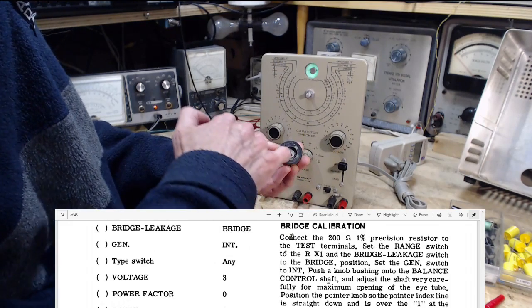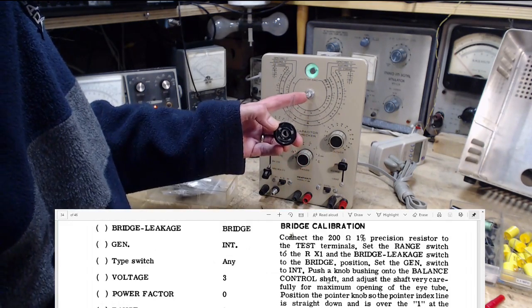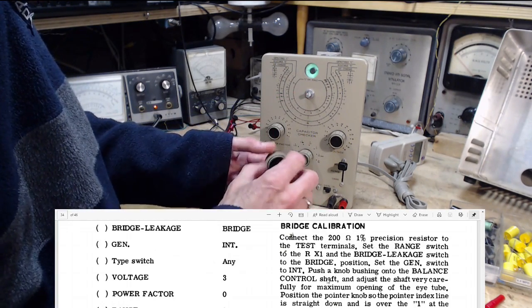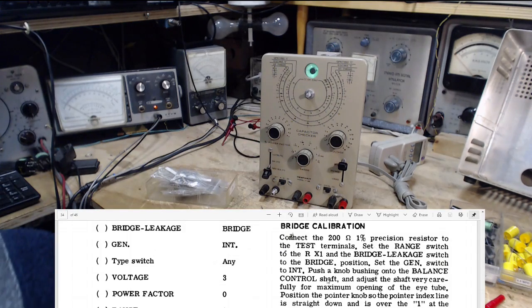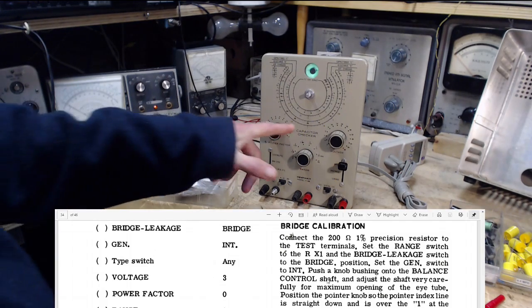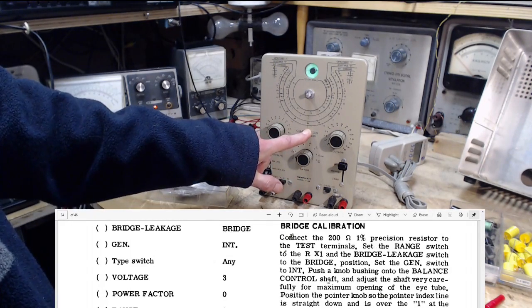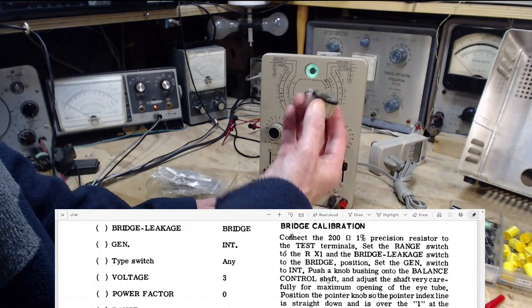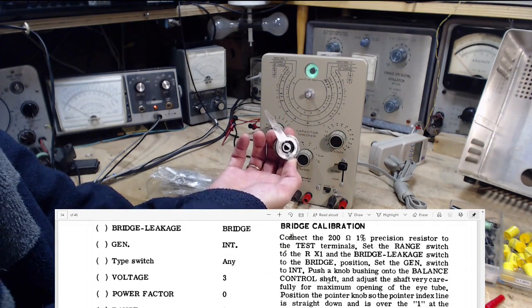I get the impression you're supposed to have that onto the knob. And then you... What's it say? It says, adjust the shaft very carefully for maximum opening of the eye tube. Position the pointer knob so the pointer index line is straight and down and is over the number one. Right there, number one. So this is a calibration of the knob position, and it's already in.